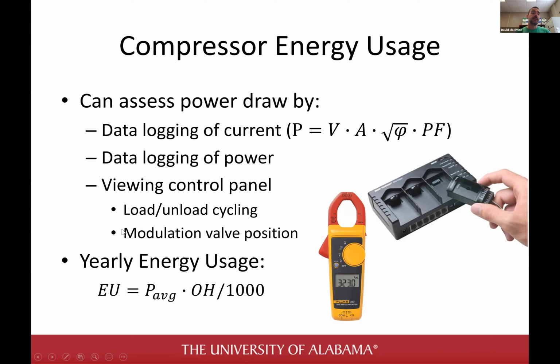So get excited. Anyway, let's say you can find out the power being drawn using this equation, which gives you power drawn in watts. If you want to figure out how many kilowatt hours your compressor is using, you divide that by 1,000 to get kilowatts, then multiply that by the number of operating hours, OH, and that way you get kilowatt hours per year.